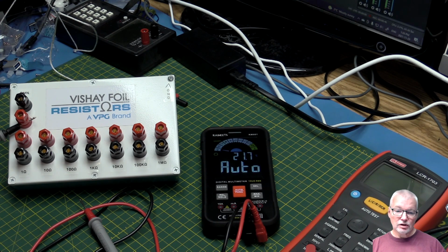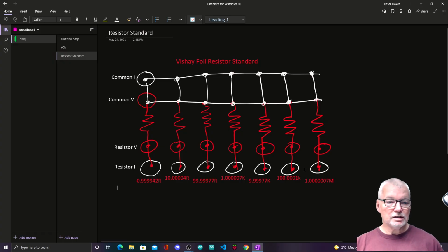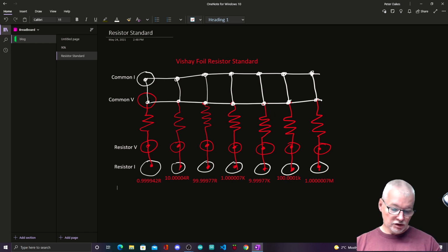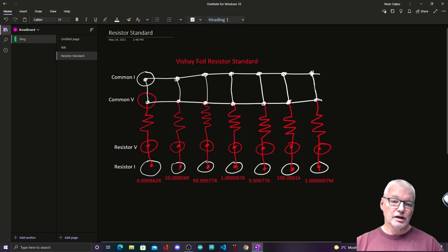Let me just quickly show you what the wiring is like inside of this. It's just a crude diagram. Basically, inside the resistance standard, we've got the common connections at the top. There are just two posts for that, and they're connected together. This is a setup so that you can do 4-wire resistance measurements as well as just 2-wire. The top of all of the resistors in this standard are common together. It's perfectly fine as long as you're not trying to use two different resistors at the same time. And we have 7 resistors: 1 ohm, 10, 100, 1K, 10K, 100K, and 1 mega.